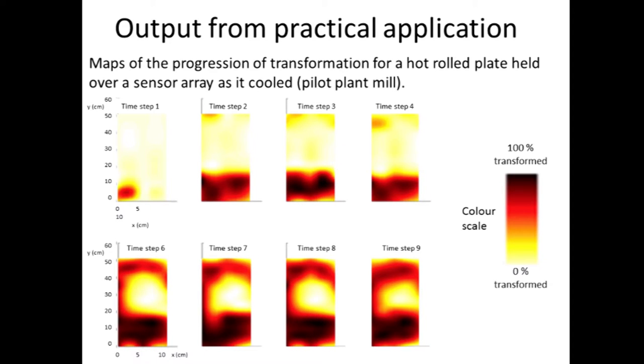Here's an example using an array of sensors for rolled plate material in a pilot plant mill at Tata Steel, coming out hot and going over a bed of an array of sensors. We can map the transformation on a colour scale — both as it's happening over time and spatially, in terms of how cooling might affect it. Also importantly, electromagnetic techniques are not sensitive to water spray or dust, so we can put them in quite aggressive environments — which is a nice advantage.